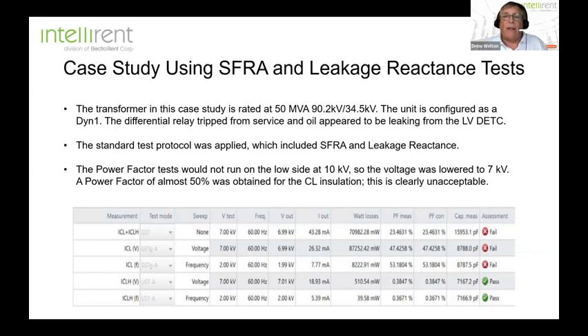Now, here's just a case study on a 50 MVA transformer where the very first thing they did was run their power factor test, and at 10 kV, it wouldn't even run. So they lowered it to 7 kV, and the power factor was almost 50%. Now that we know is totally unacceptable.